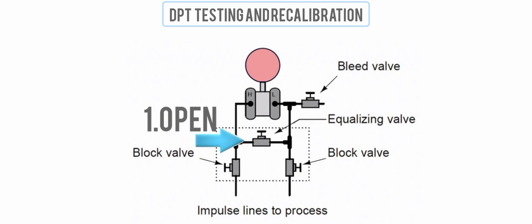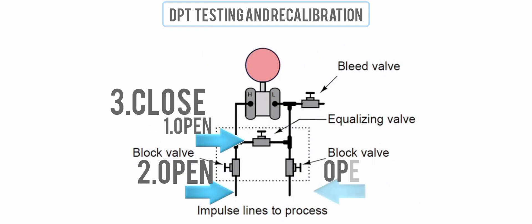By opening the equalizing valve first, then opening the high pressure block valve second, followed by closing the equalization valve, and finally opening the low pressure block valve.